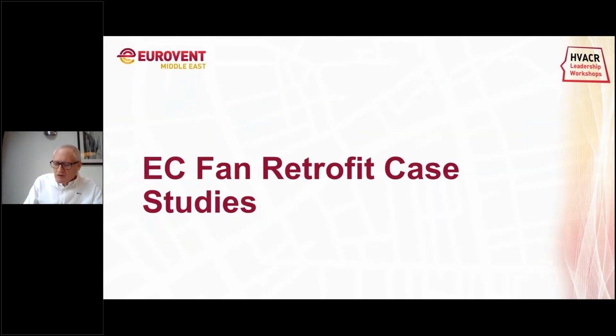So I'll talk to you a little bit about a couple of case studies we've completed with partners. I think Frank talked earlier about taking a holistic view on the system, and I'd like to endorse that. When we take up a retrofit project in a supermarket, we would always work with the refrigeration contractor, and to be honest, as Frank said, the compressors take by far the most energy. But I believe by optimizing the fan speeds and the fan, you can then modulate the pressures in the system, making the compressor a lot more efficient.